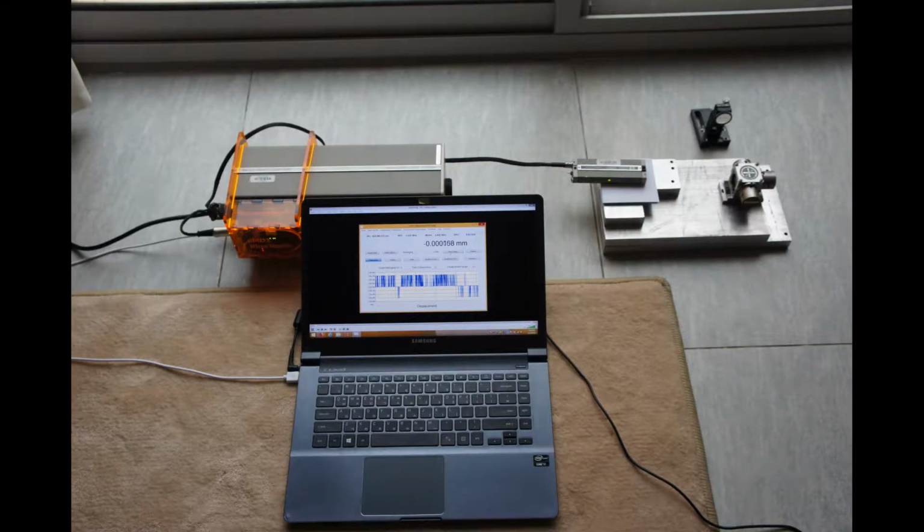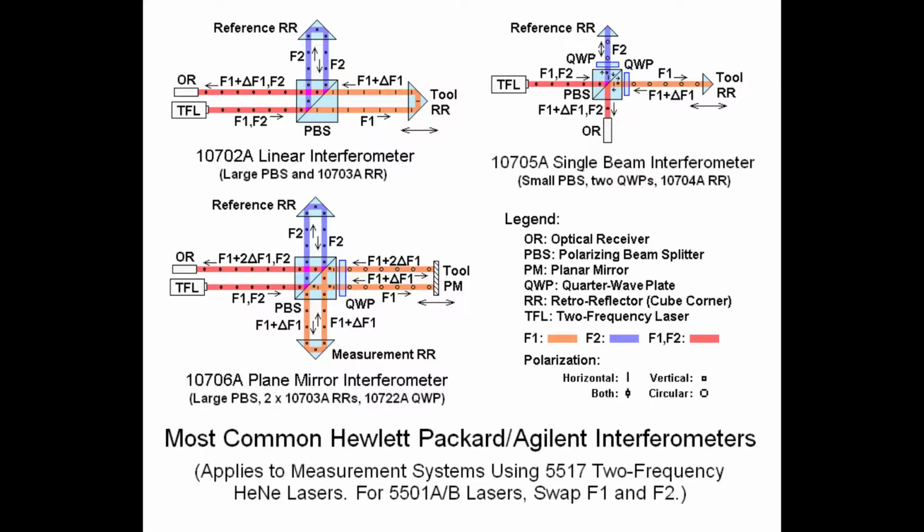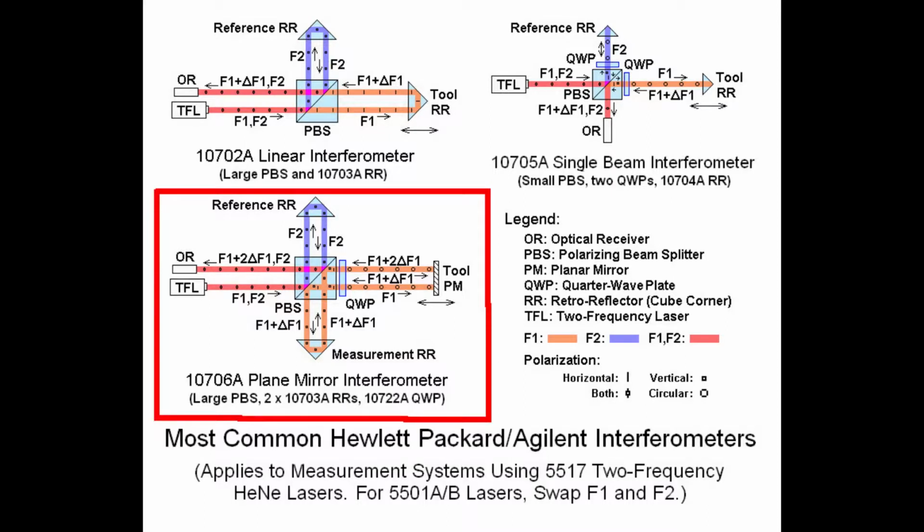This is a laser interferometer. Here, I am using a µMD1 measurement unit interfaced to a computer via USB. There are several ways to set up a laser interferometer with the HP system. In this particular case, we have a plane mirror interferometer setup.